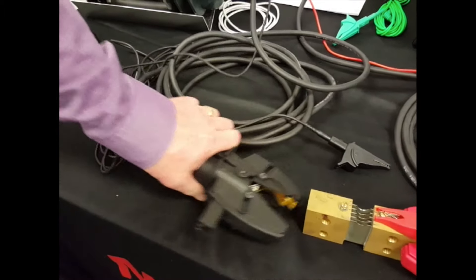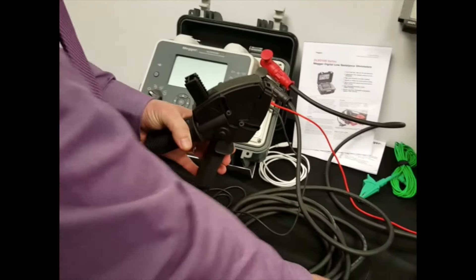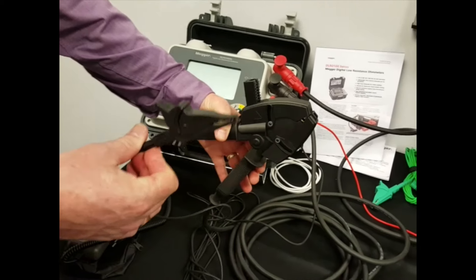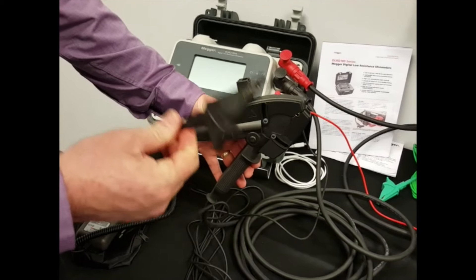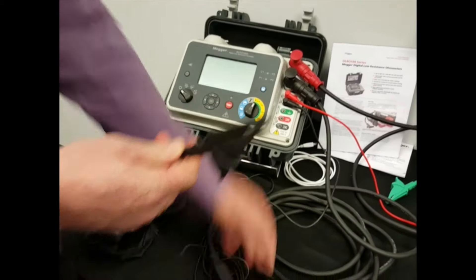Another key feature is having Cat4 600V test leads which are touch proof to IEC 61010-031. It's very important these are touch proof. Why is that?